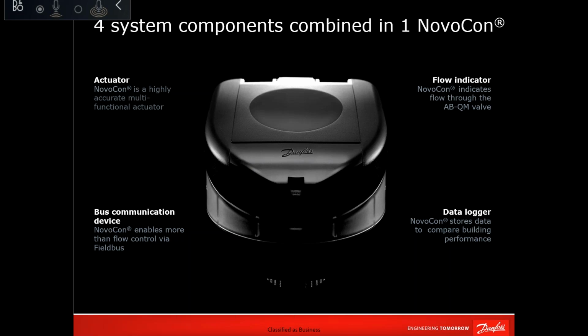So what will this give you extra is the flexibility to design your sequence of operation based on what is the load demand and what you want to achieve in your system. Let's say during peak summertime, you need maximum flow, maximum cooling capacity. The actuator can be programmed to override everything and to provide that. And during part load condition, you don't need that much, and you can achieve the same comfort level with even higher supply temperature. You can also program that in the actuator. So there is no more need for an operator to stand there, reduce, increase, change the variable, etc. This can be programmed once and the actuator will work automatically.